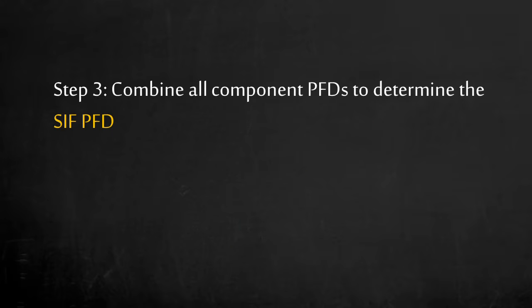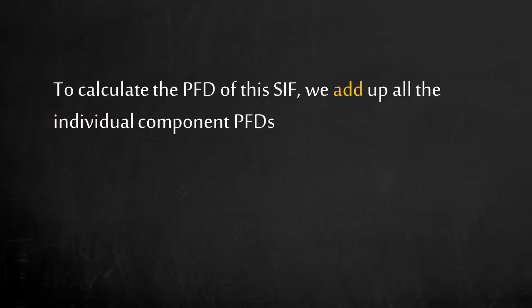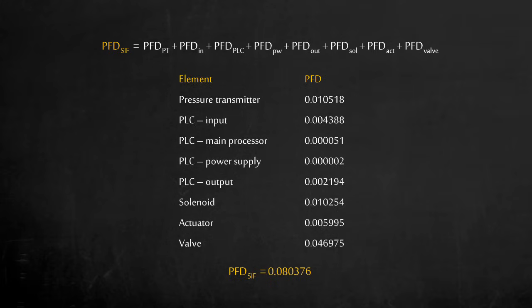Step 3. We need to determine the safety instrumented function's PFD as a whole. How do we integrate them to reflect the entire function? It's simple. For our example, the PFD of the entire safety instrumented function is just a summation of each component PFD. This only applies if there is no redundancy. The probability of failure on demand of the entire safety instrumented function is 0.080376.